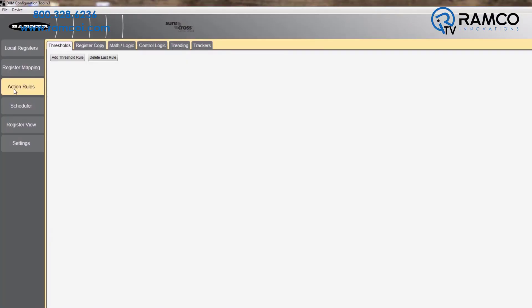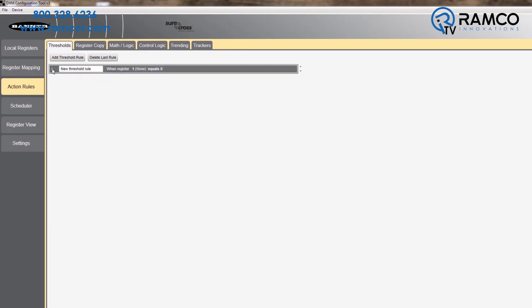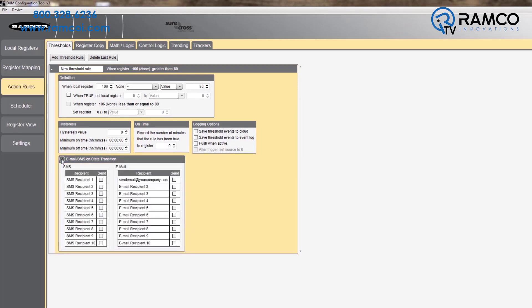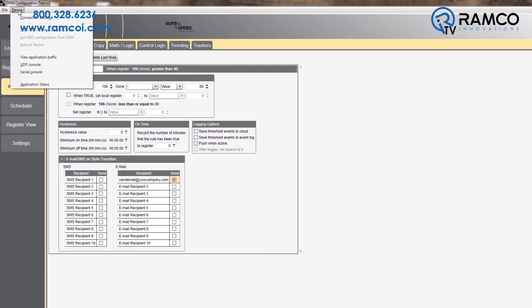Under Action Rules, select Add Threshold Rule. Enter in the desired alarm value for your device you are monitoring. Then, under Email, check the box for the message you would like to send that corresponds to one of the 10 messages you created. Finally, download the configuration and the setup for the DXM is complete.